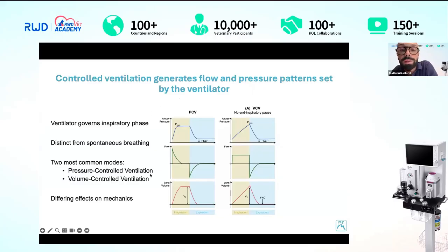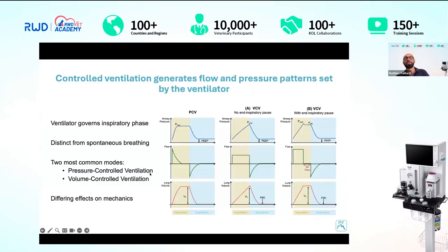When I use volume control ventilation, I can use it either without an end inspiratory pause or with an end inspiratory pause, where the tidal volume could be insufflated over a shorter duration compared to the full inspiration, and that would potentially allow some of the gases to redistribute a little better in the lung.